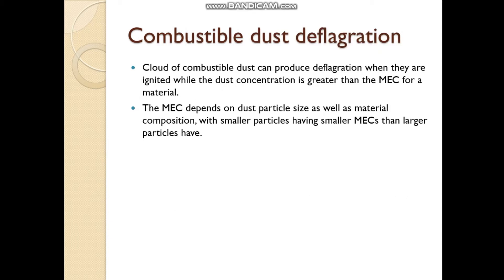Combustible dust deflagration: when a cloud of combustible dust is produced and ignited, and the dust concentration is more than the minimum explosive concentration (MEC), a deflagration can occur. The minimum explosive concentration depends on dust particle size and material composition — the smaller the particle size, the lower the minimum explosive concentration.